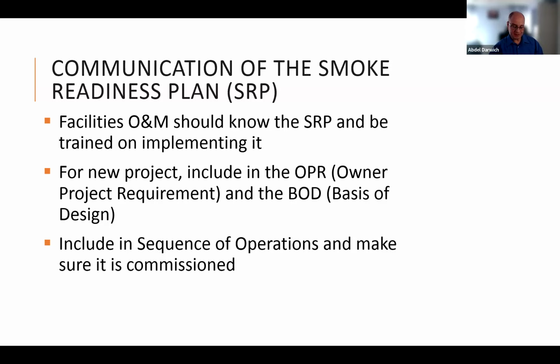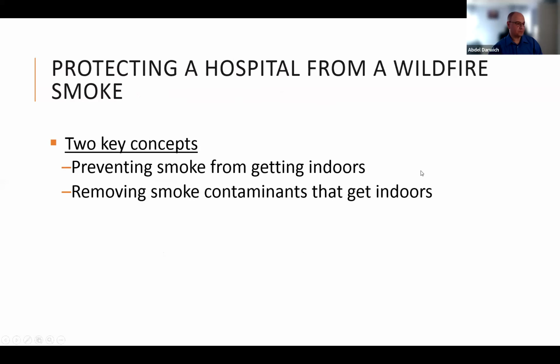For a new project, we typically develop a document called the owner's project requirements and basis of design. The owner has to tell the design team, if designing a new project, that they want the building to continue operating during wildfire smoke, and provide the smoke readiness plan so the building can be designed accordingly. Now, in many new projects, the HVAC sequence of operation includes a smoke mode, defining how the system is supposed to operate in case of smoke.